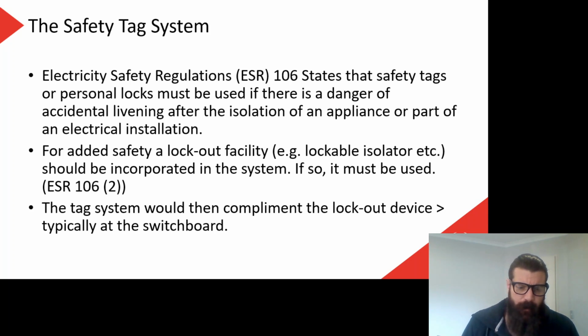Remember, of course, that when people accidentally turn things on while you're working on them, it's not usually malicious. Well, it's never malicious. They do it by accident because they see that it's switched off and think, oh, my circuit's not working. What's happened here? Oh, there's a circuit breaker off. I'll switch that back on. So that's why we have to have those tags. That's why we must have locks. And it's happened to me once before where I didn't lock something out, and somebody came in and switched that circuit on. Fortunately, I didn't get a shock, but I could have, because they switched it on because I had not locked and tagged it.